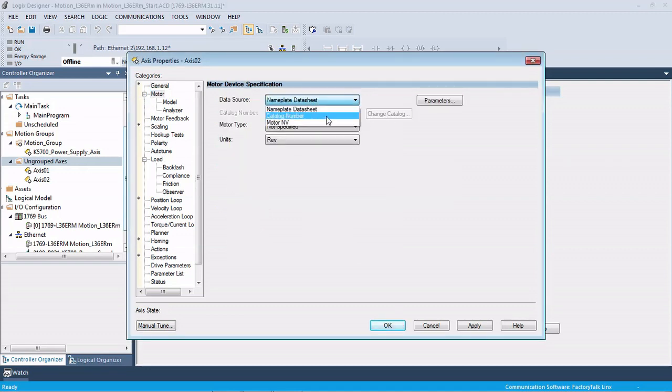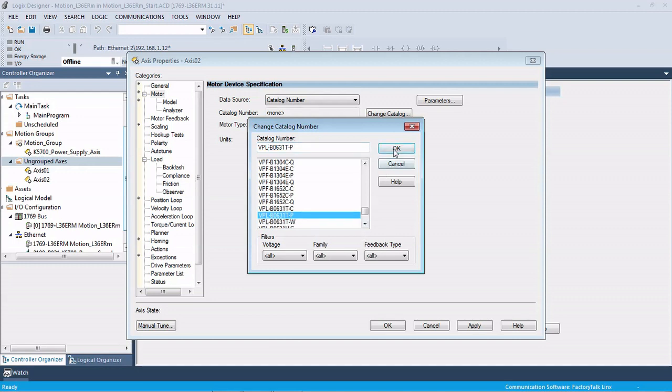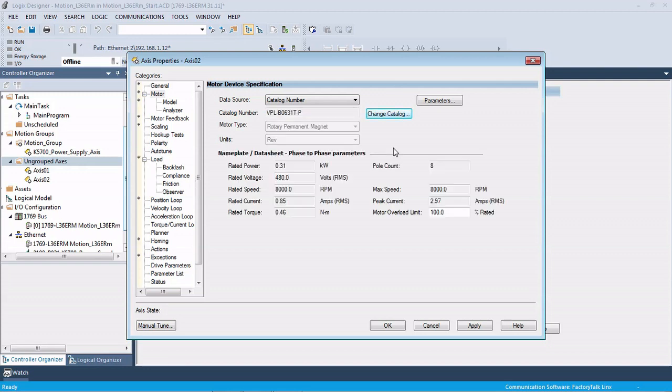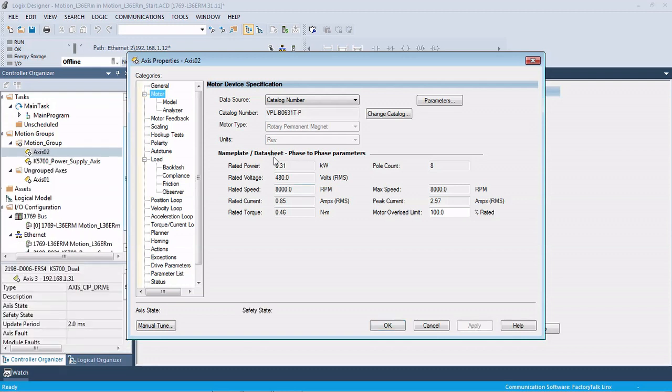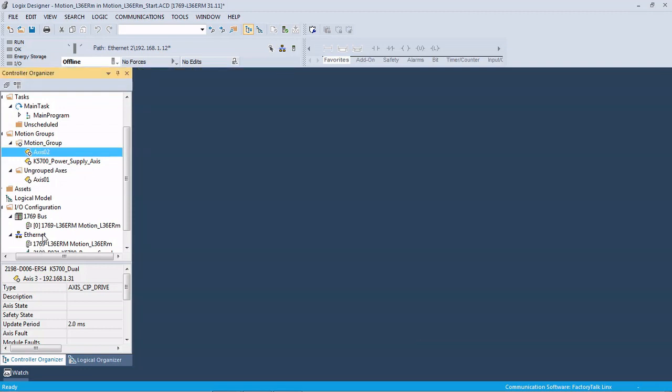Coming down to the motor, this one is a slightly different motor, the P model. So you can see the advantage here - you don't have to know any of this information. Since it's a Rockwell servo, it all populates automatically. It used to be you had to come in and put all the motor information in manually and do a lot of calculations. Everything loads for you and gets you very close. So now we're set up and ready to download.